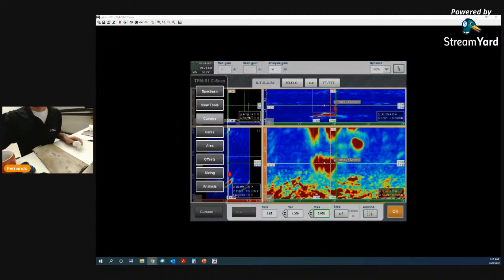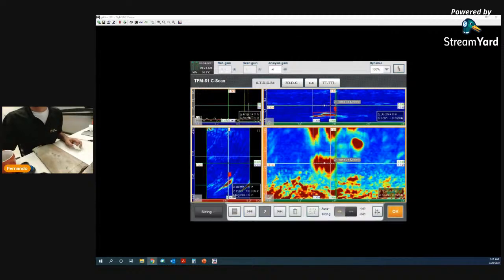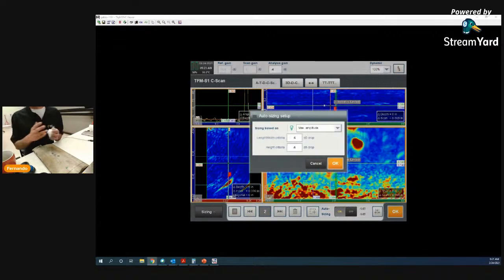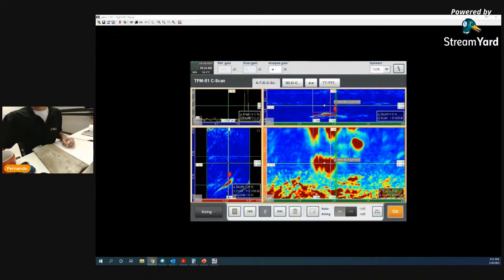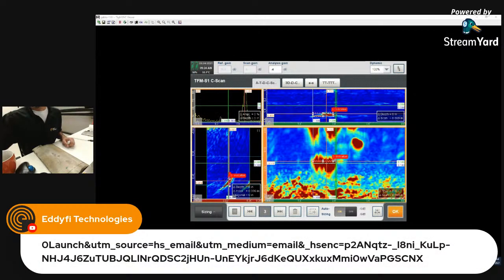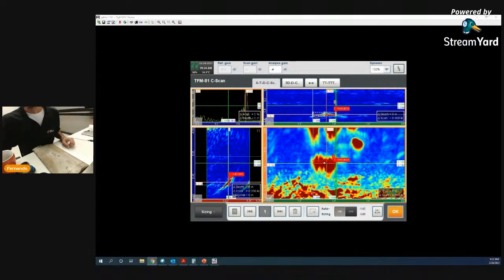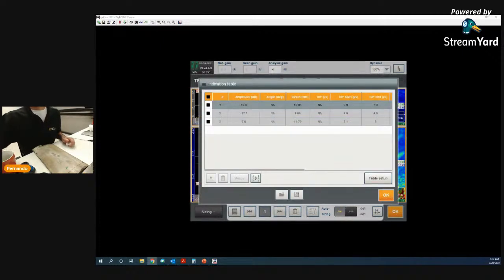So you have gate adjustments. You can adjust the offset. The other thing you can do with the software is automatic sizing. You can do -6, so you can choose a parameter. If your procedure says -20, you can adjust it to that. You would choose your area. See, I want to adjust it there. It automatically sizes the thing. And then you can see I have 3 indications here.